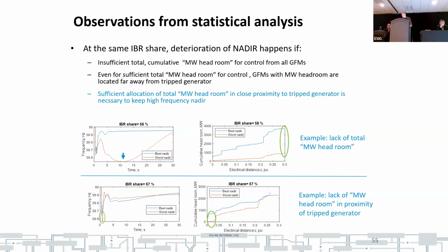On the bottom line, you see another phenomenon, which is showing the locality of headroom. On the horizontal axis of this curve is the electrical distance from the generator that was tripped as a contingency. So if you have a sufficient amount of megawatt headroom for control in close proximity to that generator, it will greatly improve the nadir of frequency. And on the opposite, if there is a hole, I mean, a lack of total megawatt headroom for control, that results in deterioration of nadir.